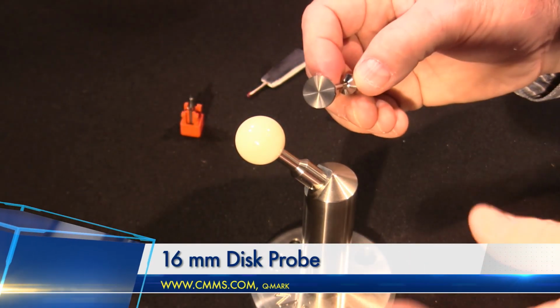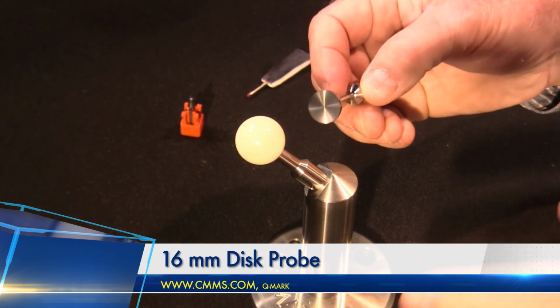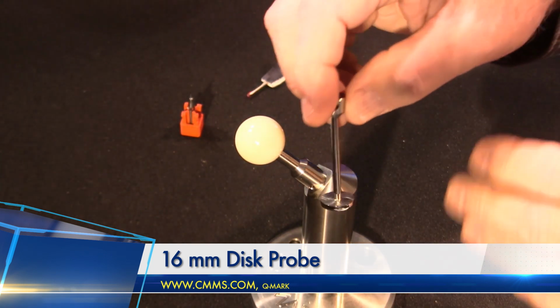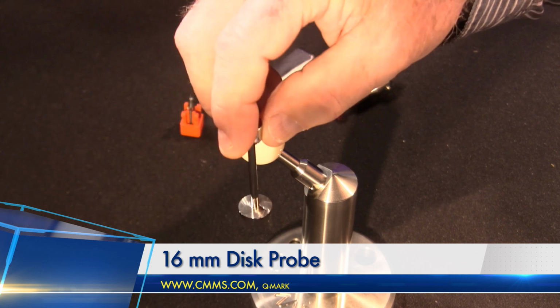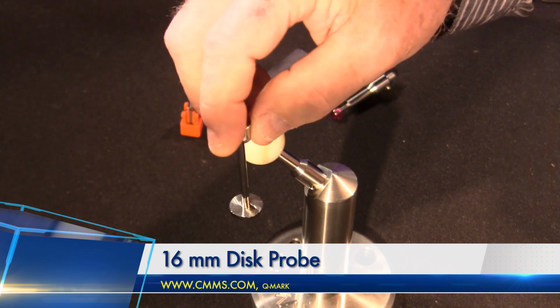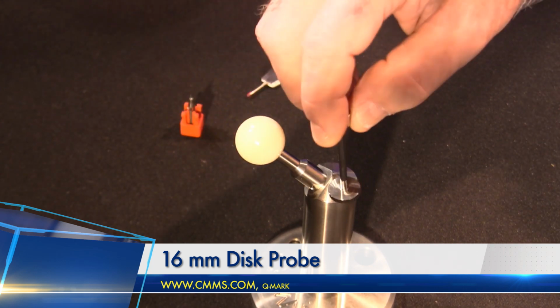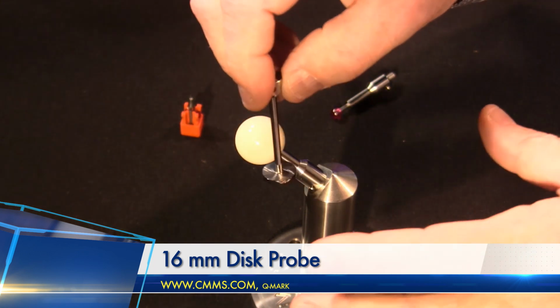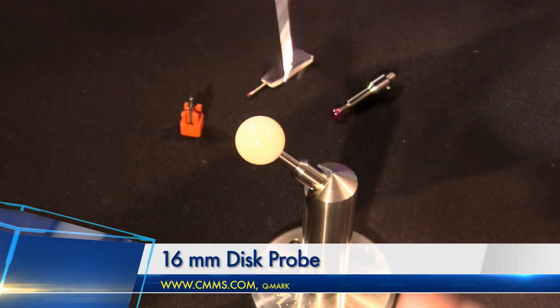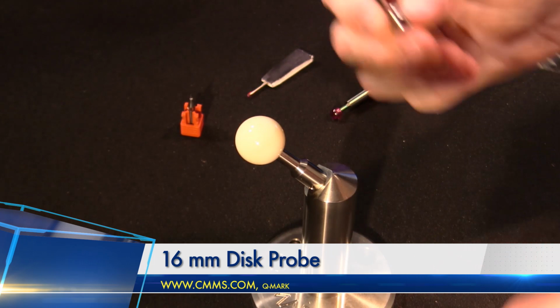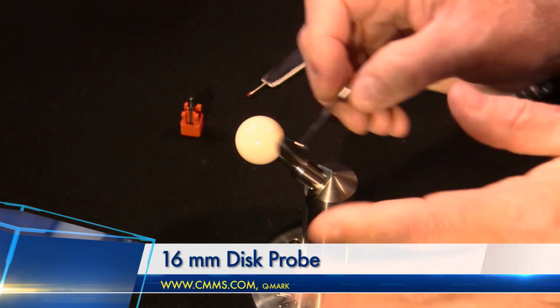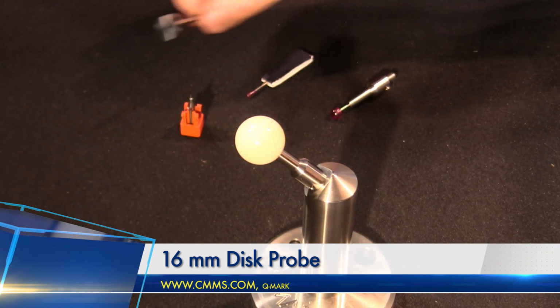Now, when you're done with that, common sense dictates and QMark suggests, you should now go out and actually measure a known artifact, so maybe a gauge block. So you might go out and take some measurements on a gauge block and make sure that the data you get back is the data that you expect. This is just a way to verify that your calibration went the way it should have.